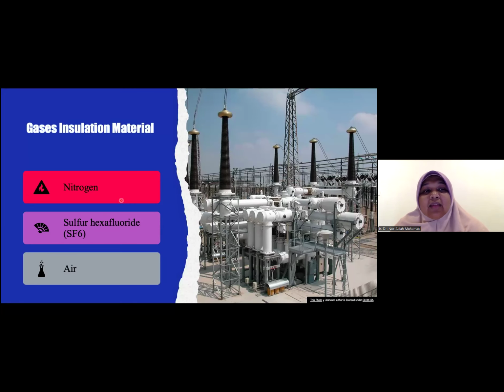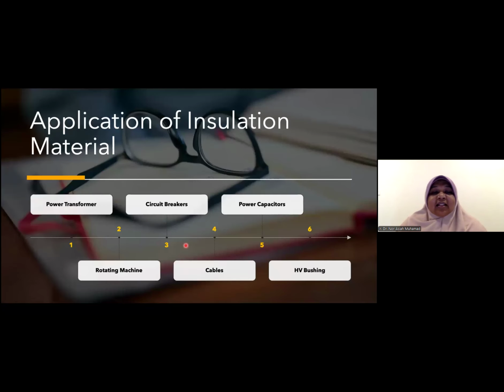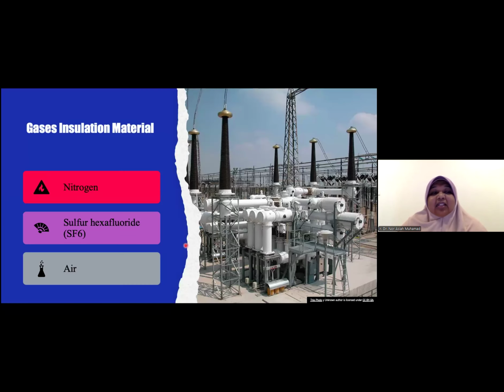We also have gas. The third major insulating material is gas insulation. So this is SF6 switchgear. Inside this pipe there is gas, where every time they are disconnected, this gas is used to insulate the connection. We have 3 major types, which are nitrogen, SF6, and air. Air is also considered a gas.